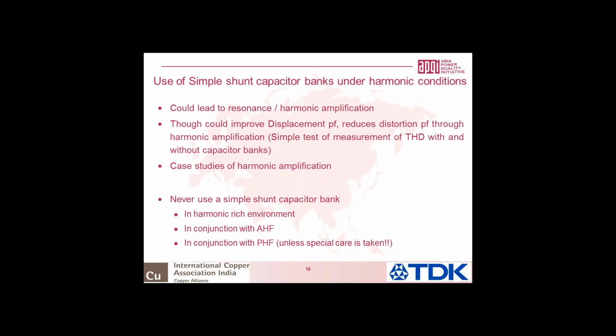For example, his 11th harmonic was almost 43 ampere. 7th harmonic was 17 ampere. 5th harmonic was 17 ampere. All I did was disconnect the capacitor bank, and you saw a sudden reduction in the current. 43 ampere of 11th harmonic came down to 3 ampere. 17 ampere each of 5th and 7th came down to 3 ampere each, which very clearly showed that his excess harmonic distortion, for which he is now paying a penalty, is not because he has a large number of nonlinear loads. He is creating an internal resonance in the system.